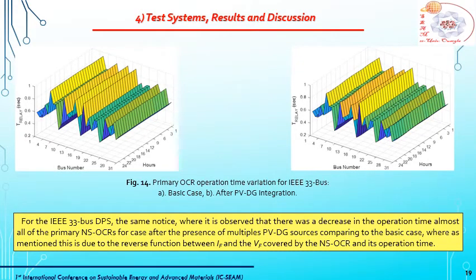Figure 14 represents primary overcurrent relay operation time variation for the second test system, which is the IEEE 33 bus. Also, the same remark here that after the integration of PVDG into DPS, the operation time is decreased almost in all of the primary overcurrent relays.